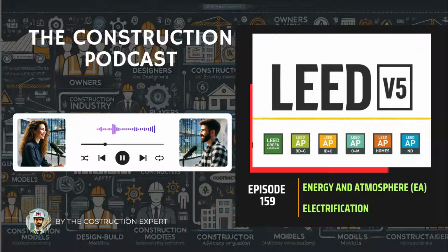It allows for resilient design in places like, say, Minnesota or Maine, where relying solely on electrics might be challenging or overly expensive on the absolute coldest days. But the bulk of the heating still has to be electric. Gotcha. Does this path also have the COP requirement? Yes, but only in climate zones 3 and above, basically, everywhere that isn't those very warm zones we talked about. Where heating is a significant load, you still need that weighted average efficiency of at least 1.8 COP for the electric part. Okay. So 2 points for electric space heating with a cold weather allowance.